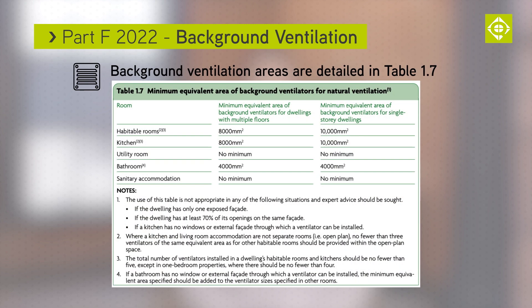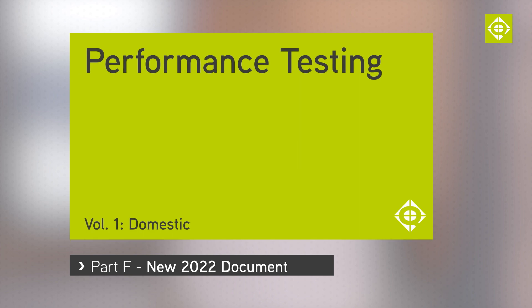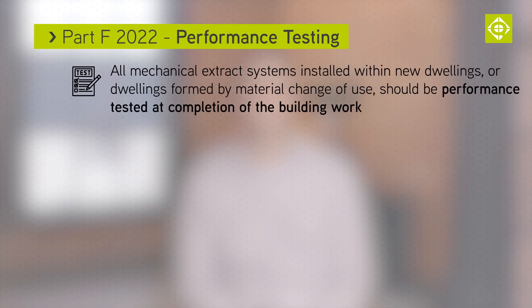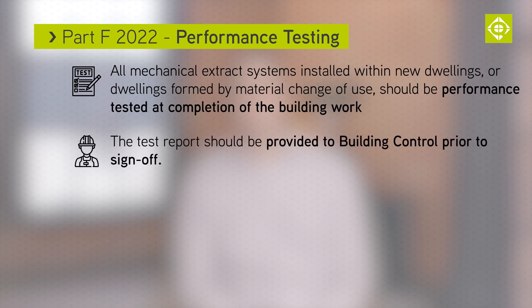Background ventilation should be provided following the guidance in Table 1.7. Figures are provided for minimum equivalent areas of background ventilation for single storey dwellings and dwellings with multiple floors. All mechanical extract systems installed within new dwellings or dwellings formed by a material change of use should be performance tested at completion of the building work. The test report should be provided to building control prior to sign off.